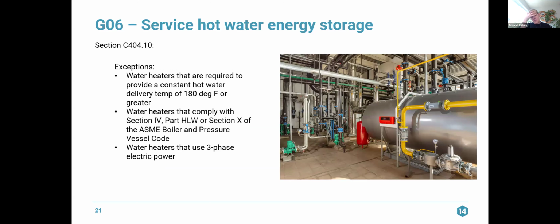There are exceptions to section C404.10. Water heaters that are required to provide a constant hot water delivery temperature of 180 degrees or greater, and water heaters that comply with Section 4, Part HLW or Section X of the ASME Boiler and Pressure Vessel Code are not required to have demand response. Water heaters that use three-phase electric power are not required to comply with the demand response section credits in Section 404.10. Because they are not required to comply with Section 404.10, they can achieve greater credits for complying with the renewables and load management service water heating credit.